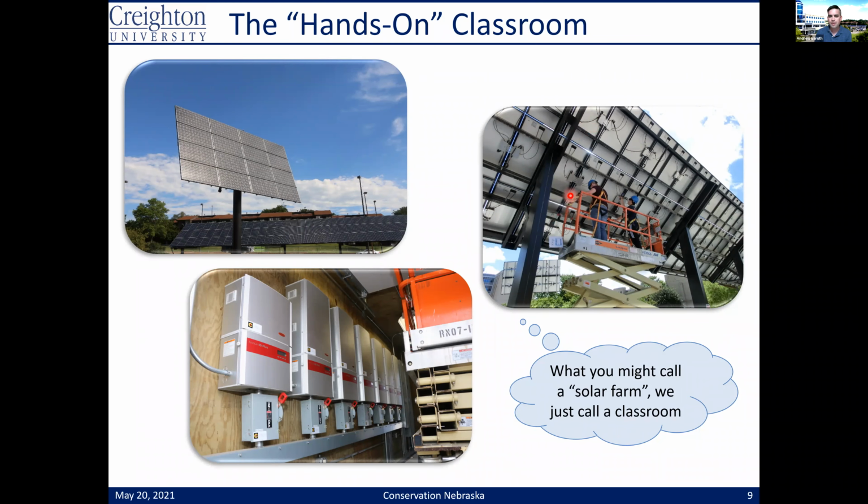Alternatively, we have additional panels that do not get inverted right at the panel site, and they go in what we call strings, and they all go back to what we call string inverters. So these string inverters, on the other hand, can handle quite a few panels. So maybe 3 to 5 strings, where each string might have 12 to 15 panels on them. And so this, for example, is a 7 kilowatt inverter. This is a 3 kilowatt inverter. And so we have a variety of strings that are all coming back here.